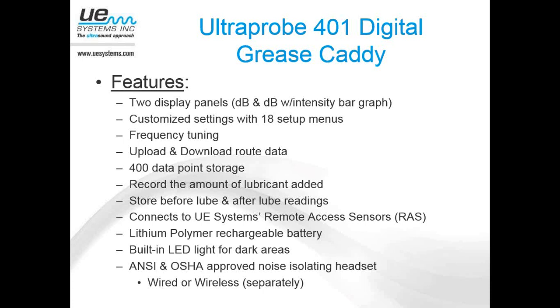We have upload and download route capability from the UltraTrend DMS software directly into the 401. So we now have data storage here, and all that's done via the SD card, same as the Ultraprobe 15,000. Just like any of the other Ultraprobes that have data storage, we have up to 400 readings per route that can be collected at any given time. We can actually record the amount of lubricant added, and we'll go into that in a little more detail when we get to that slide, but we think that's going to be a nice feature.